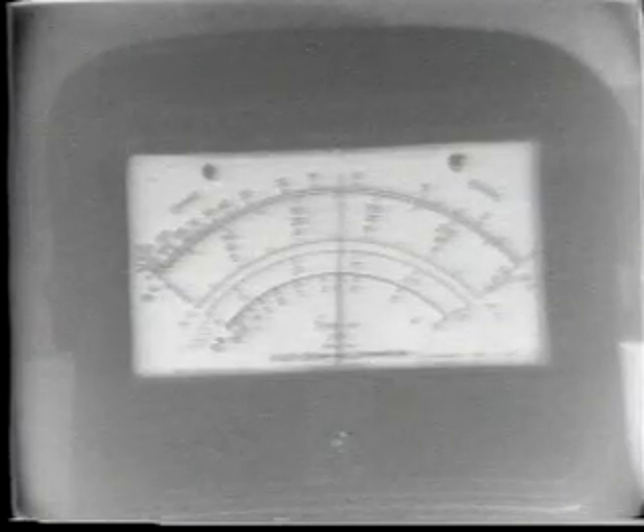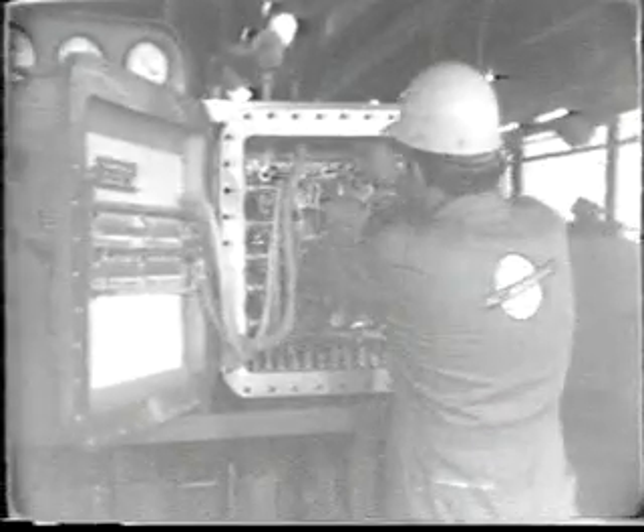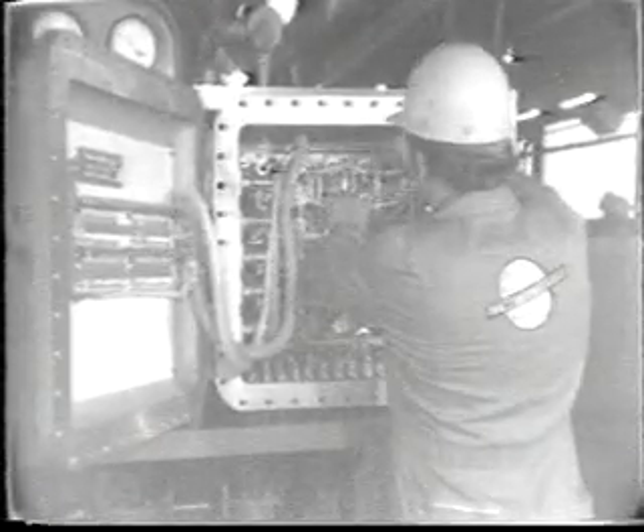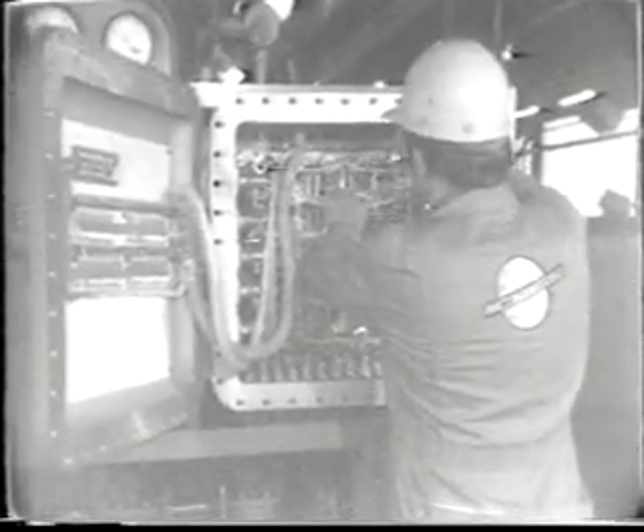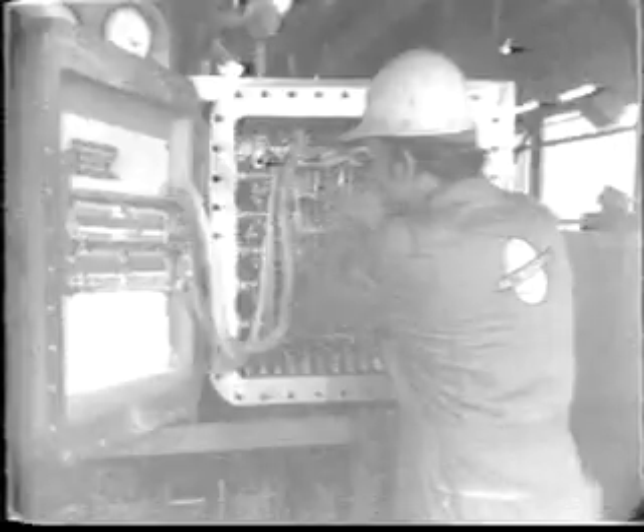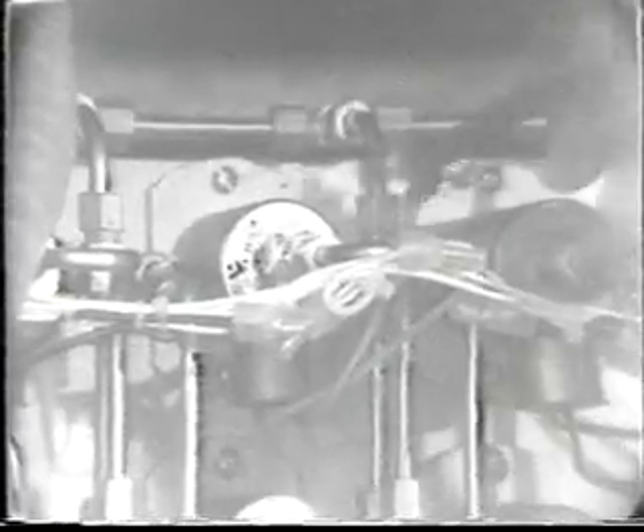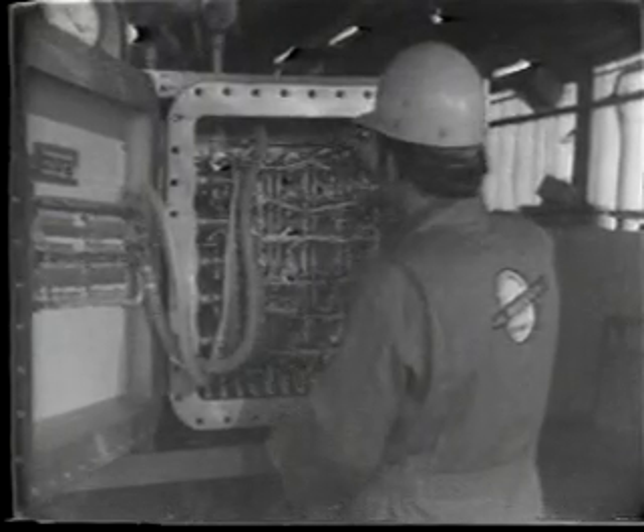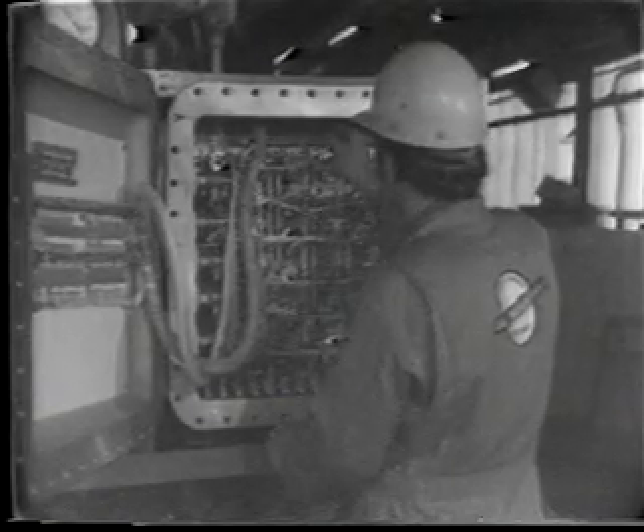If the voltage check is good and the solenoid still will not energize when the button is pushed, you should loosen the tubing at the fitting on the inlet side of the solenoid and make sure you have air pressure to the solenoid. If you have air pressure at this point, you should change the solenoid coil. This is much faster than changing out the entire solenoid.